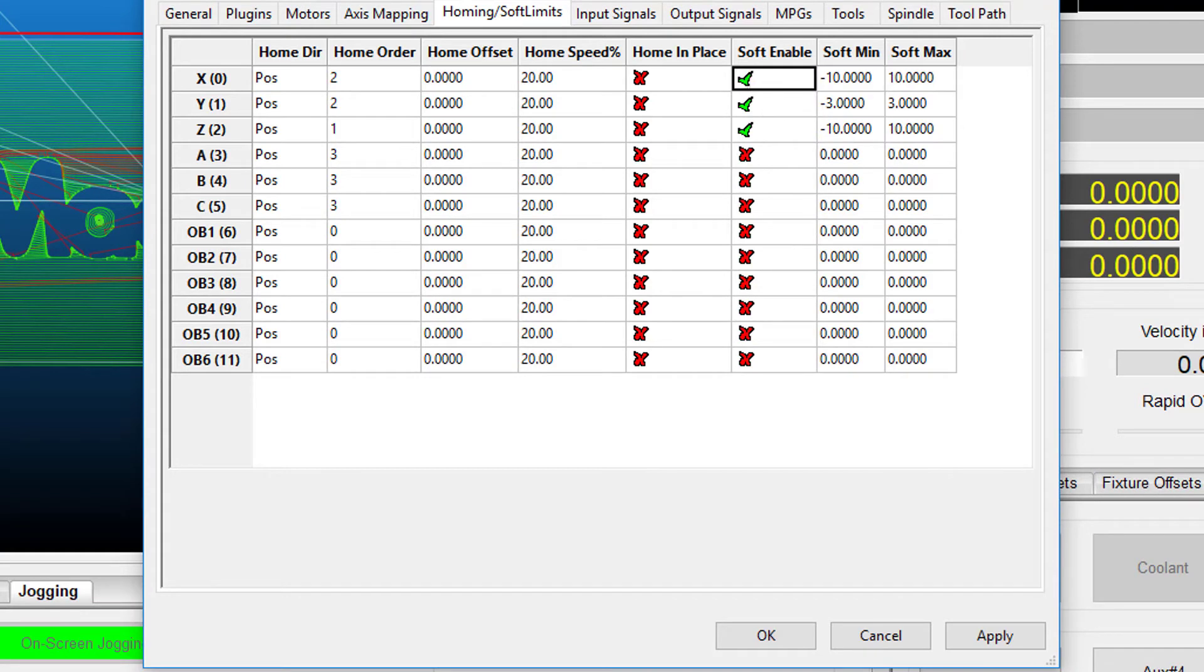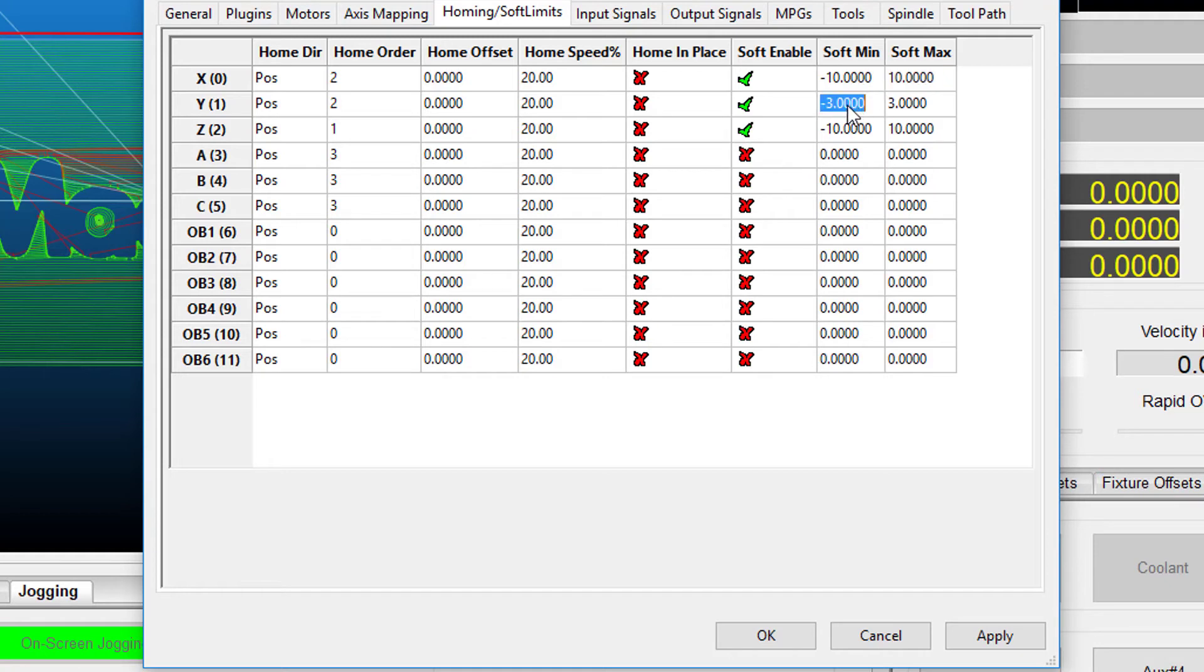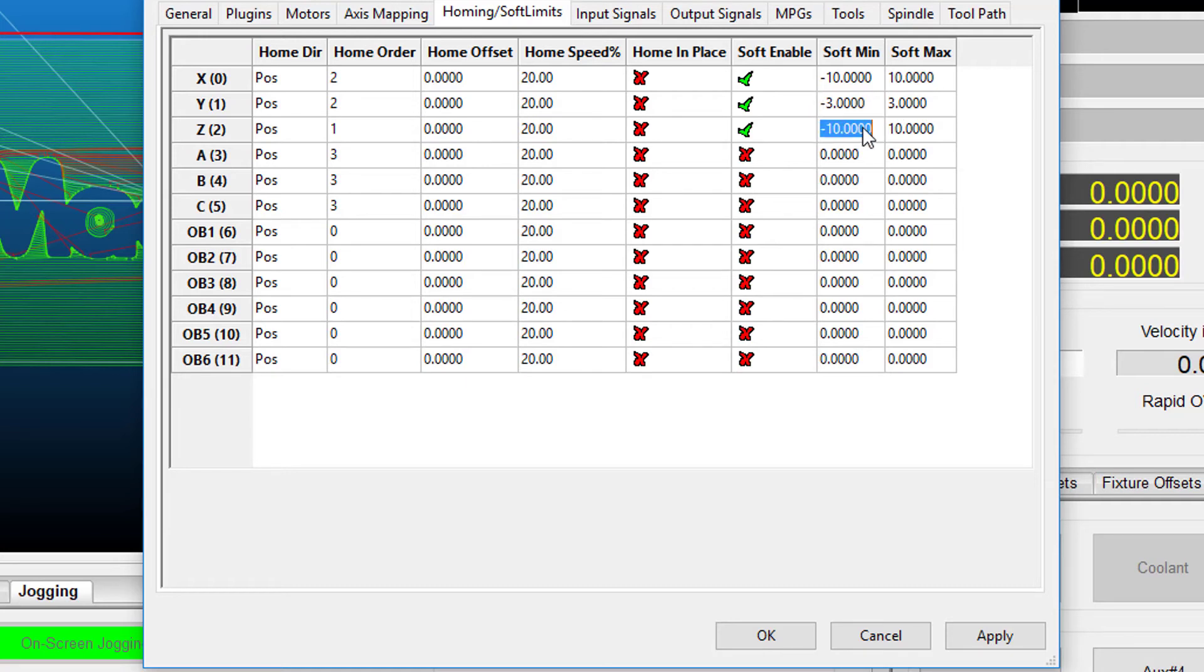Note: if the value is positive, place it into the soft max limit and set the soft min limit to zero. Otherwise, with the negative value, set the soft max to zero and the soft min to the recorded value.